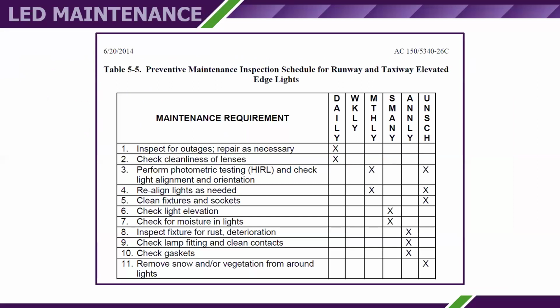This is Table 5-5 out of Advisory Circular 150/5340-26C, preventative maintenance inspection schedule for runway and taxiway elevated edge lights. And it goes through what the FAA thinks your inspection should be daily, weekly, monthly, and so on for an elevated fixture. Now, you'd also want to use this as well as any of the manufacturer's recommendations.